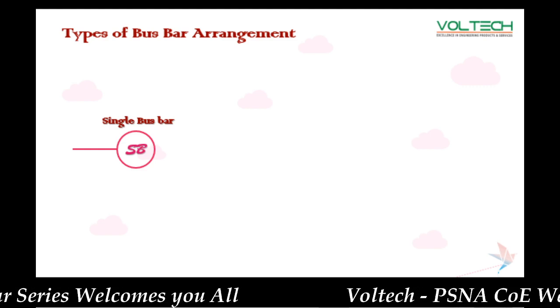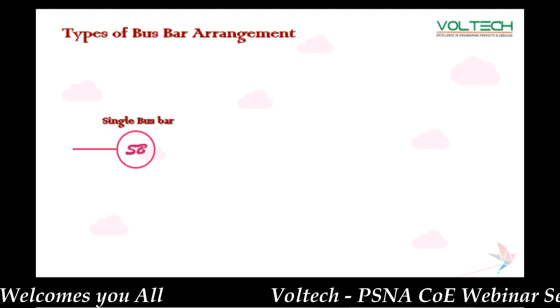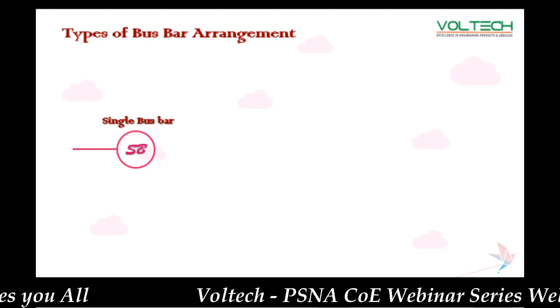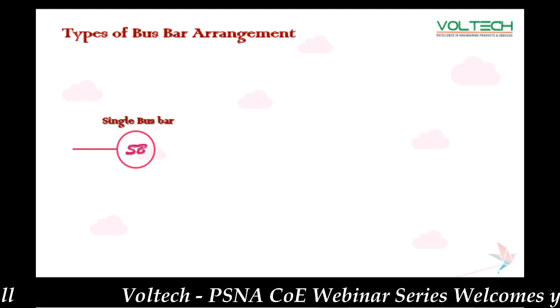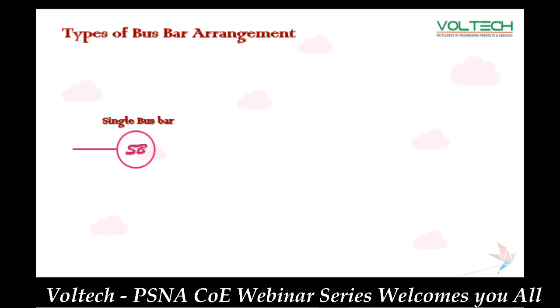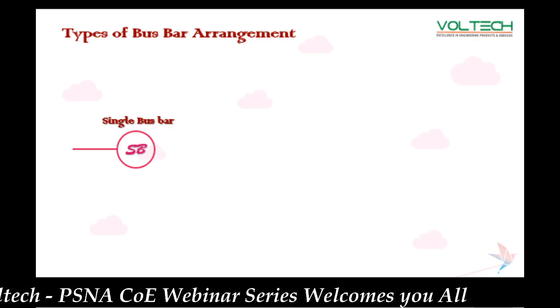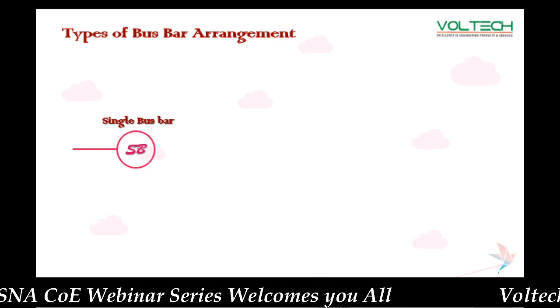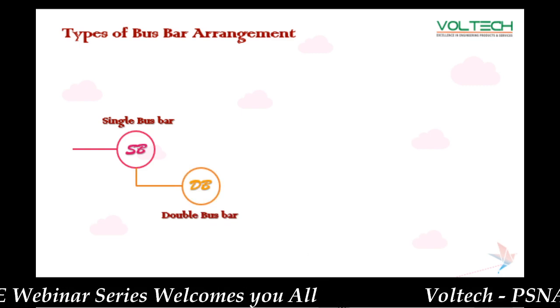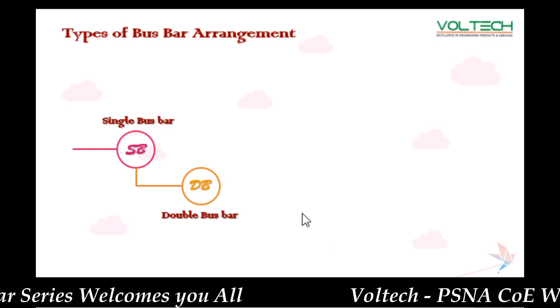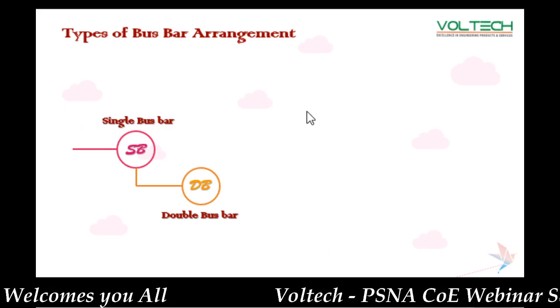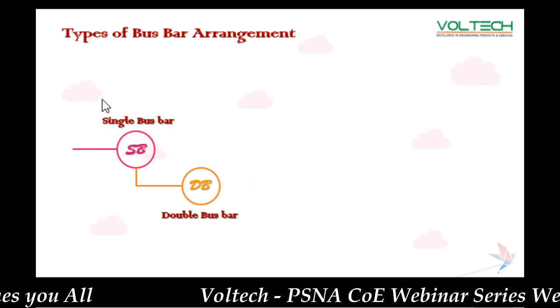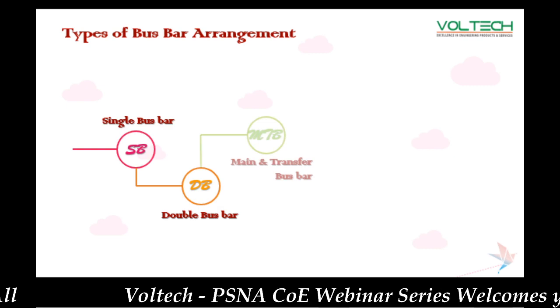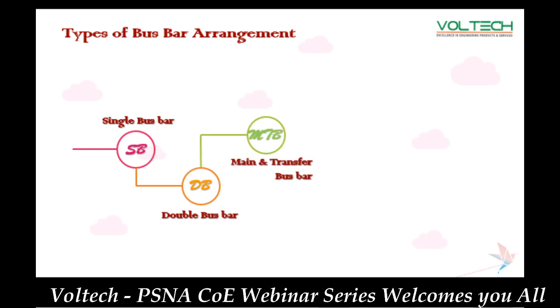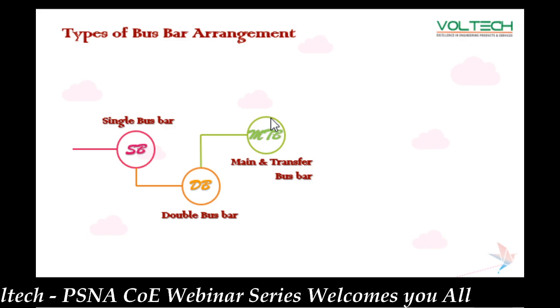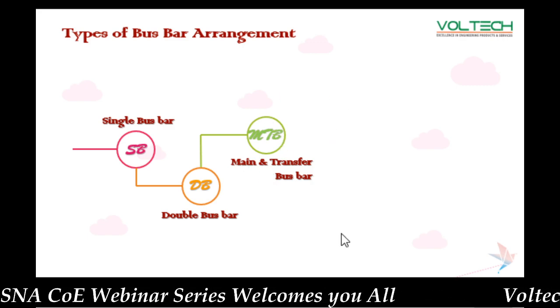So this is the single bus. Single bus means only one bus with some other feeders. Only one bus is connected and some other feeders are connected to the single bus. Then the next level is double bus. Double bus is nothing but we place one parallel bus with the single bus, one more parallel main bus. Next is main bus and transfer bus. This is the same as a double bus, but we call one a transfer bus.